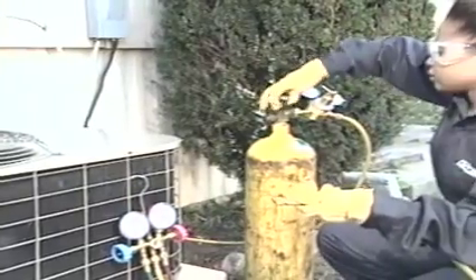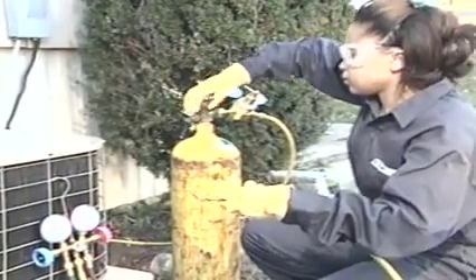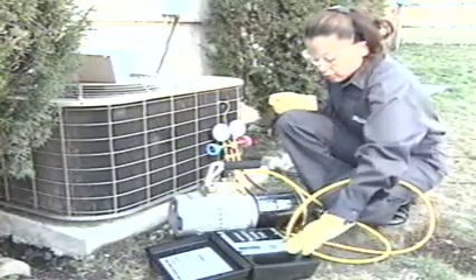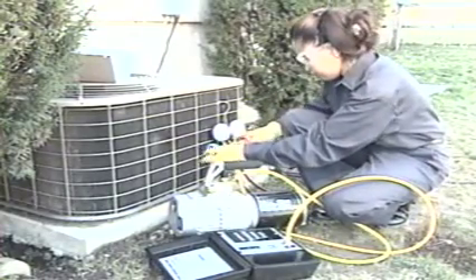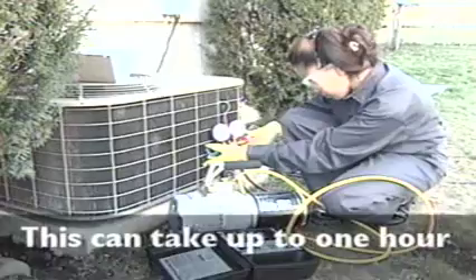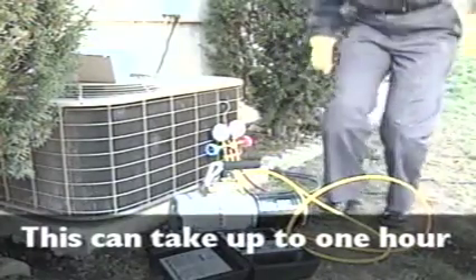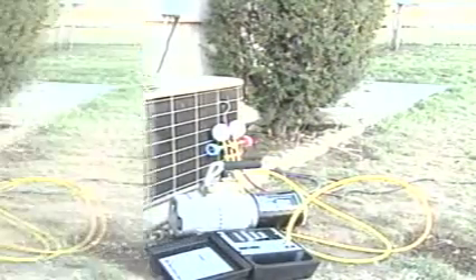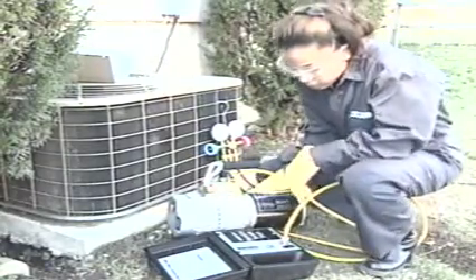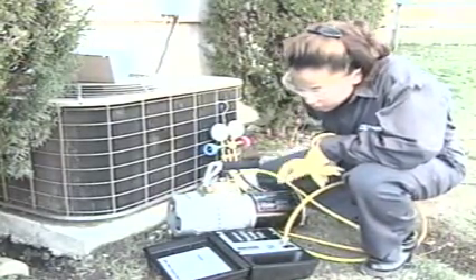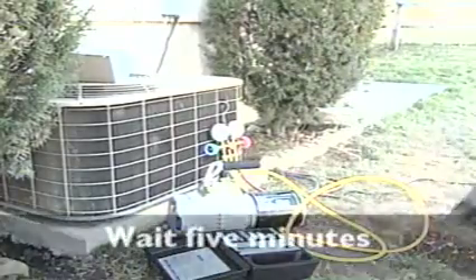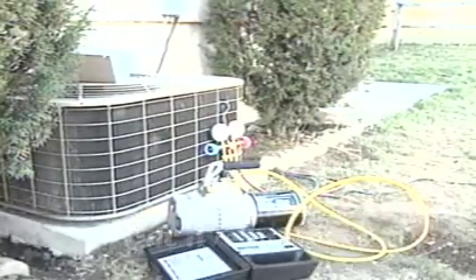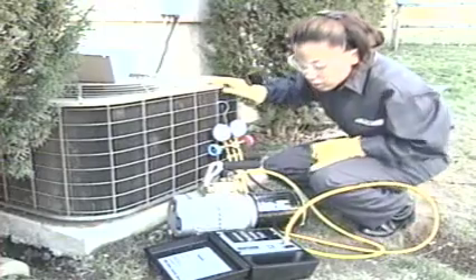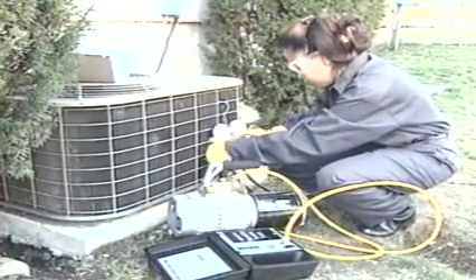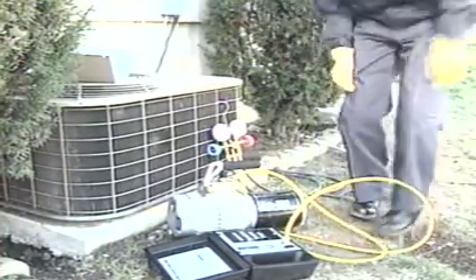Next, flush the system with nitrogen to dry it out and remove any contaminants caused by the soldering. Then, use a vacuum pump to evacuate the system to 500 microns. Finally, turn the pump off and let the system sit idle for 5 minutes to assure that it's tight and all the contaminants have been removed. Observe the compound gauge and micron gauge. They should show no rise in pressure.